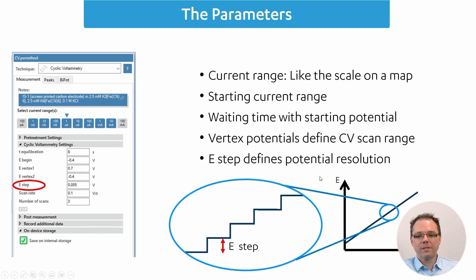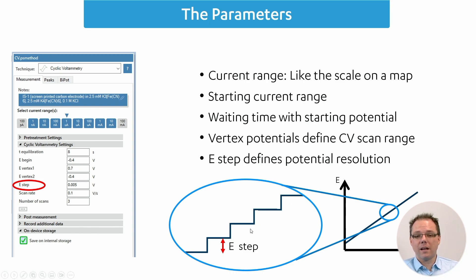The next parameter, E-step, tells you the resolution of your CV. Our potentiostats are digital, so they cannot produce a perfect continuum — they work with little steps to change the potential. So your ramp is not a perfect line but a small series of steps, and how high these steps are is defined by the step potential. With an E-step of 5 mV, for example, a point with the current value is recorded every 5 millivolts.